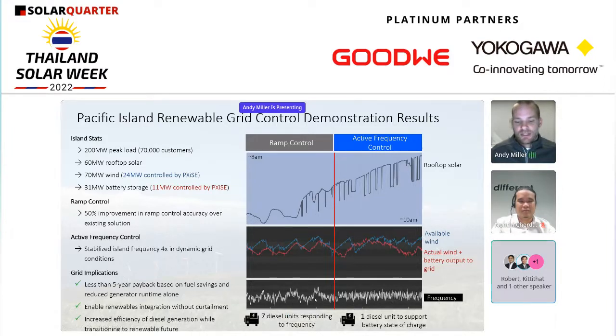Right now the grid has 7 diesel generation units monitoring this frequency variable, constantly moving up and down throughout the day to keep the system in balance. With no new infrastructure, just more intelligent control on the existing energy storage assets, we flatlined that frequency, stabilizing it by over 4x what it was before, so the diesel generation units could remain parked at their most optimal levels. This is illustrated by going from 7 diesel generation units needed to keep the system balanced down to just 1, used to backfill the battery while all the others operate as efficiently as possible.